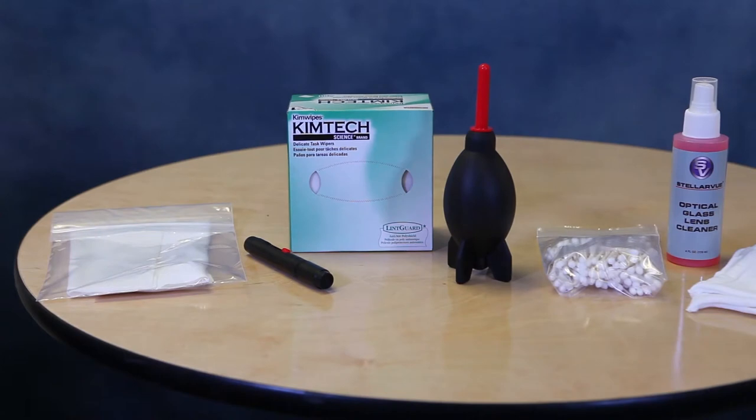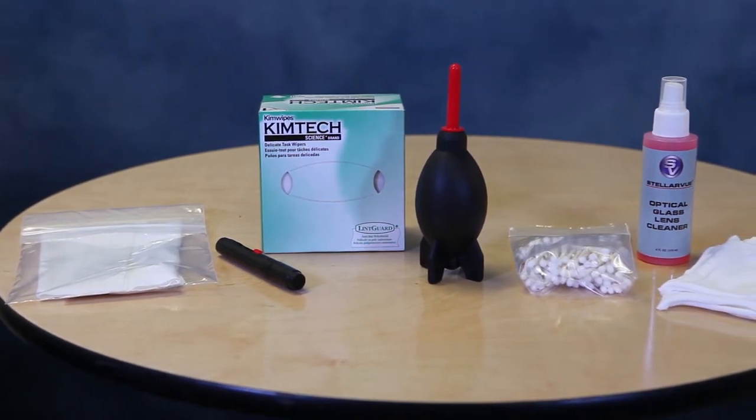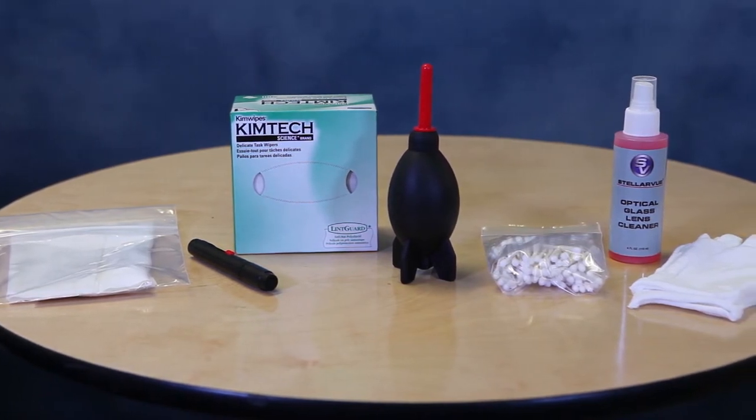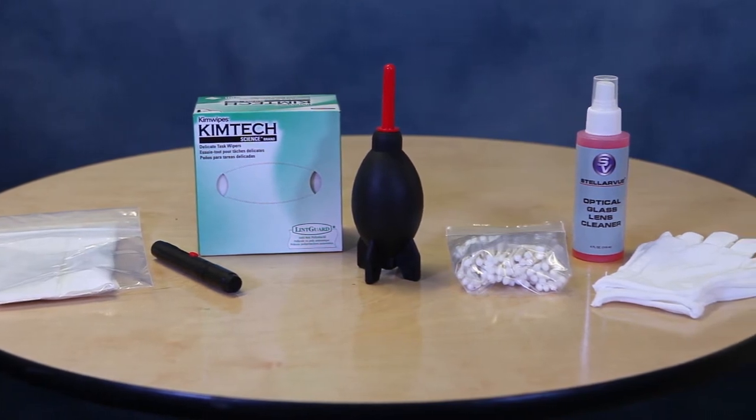To properly clean eyepieces, you need the proper tools. You need to first start with clean microfiber cloths, not for cleaning any optical surfaces, but for cleaning the eyepiece's exterior. A soft camel hair brush or a lens pen, lens tissues or kim wipes which are disposable, use once and throw away.